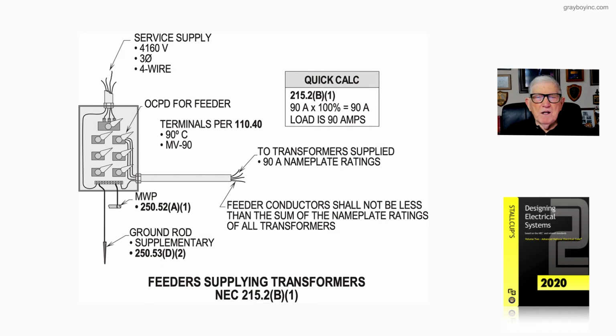Now you may say, well, I've seen plans where the engineers put 125% on. Well, they're just providing a little bit of a cushion. But notice where these feeders are routed to transformers supplied at 90 amps nameplate ratings, see? And the feeder conductor shall not be less than the sum of the nameplate ratings of all transformers. And then, of course, you can see we're grounded to a driven rod, supplementing your water pipe in accordance with 250.52(A)(1) and 250.50 of the code when you start providing and forming a grounding electrode system. And that's what this figure 17-16 is illustrating to the user of the code.